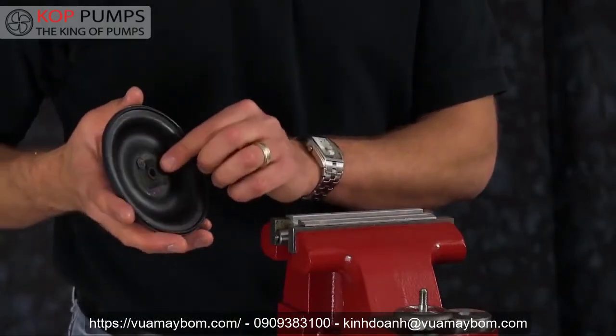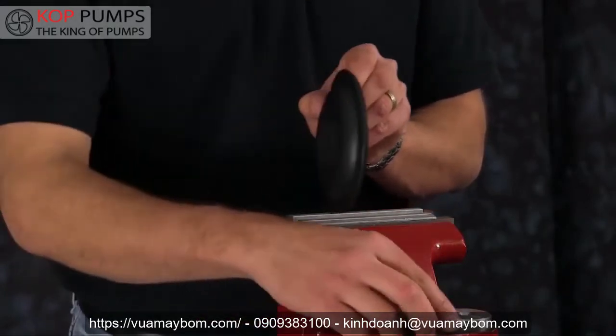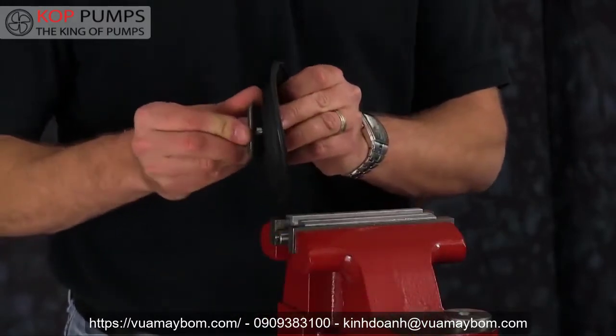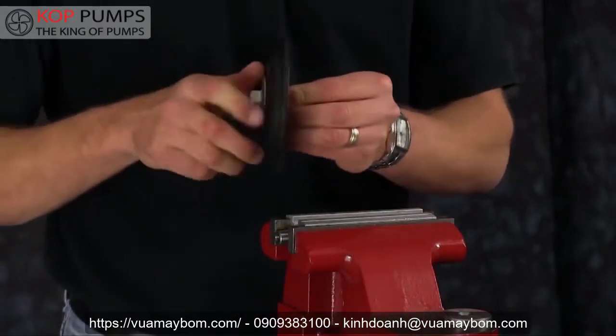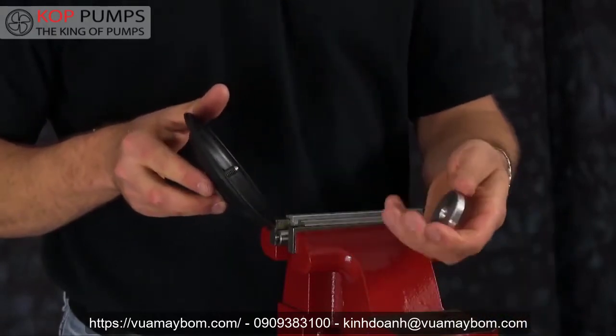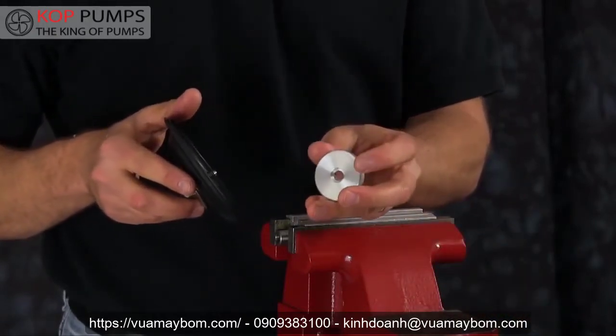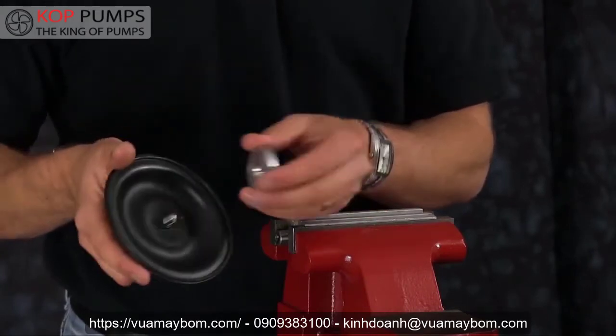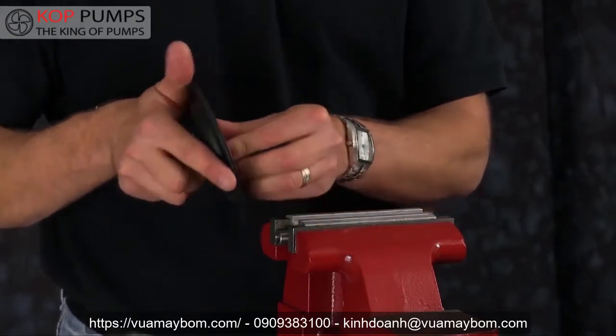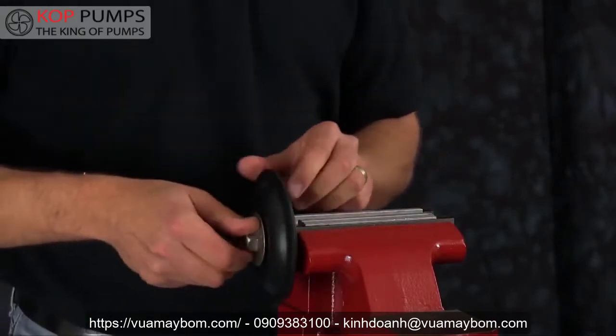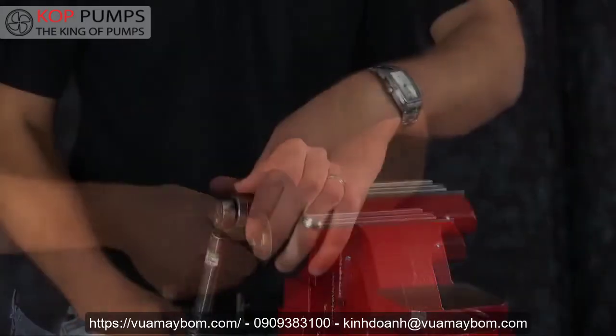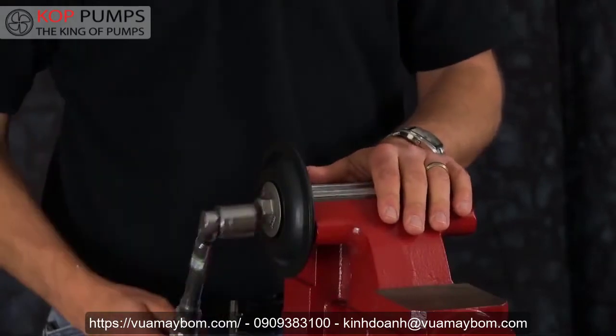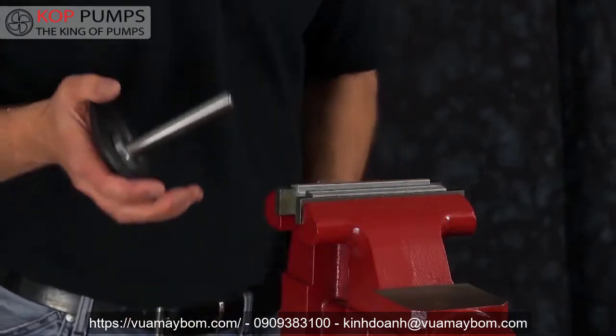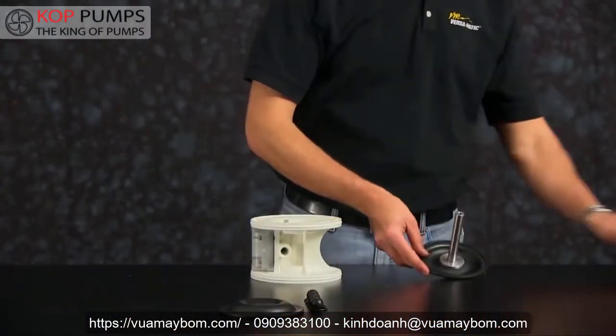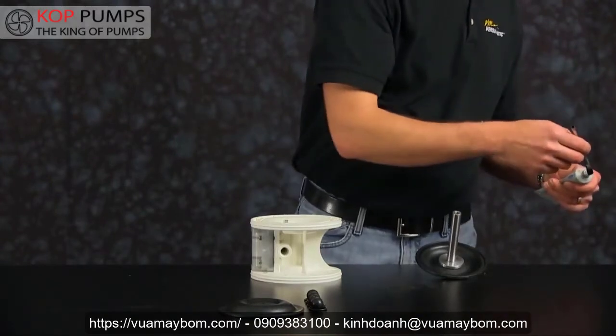Install the outer plate towards the wet side of the diaphragm. In this case, its natural bulge out. Install the radius of the inner plate towards the air side of the diaphragm. Be sure to torque the diaphragm assembly to the rod according to our torque specifications listed in the service manual. Apply grease to the main shaft to ensure we do not damage the main shaft O-ring.